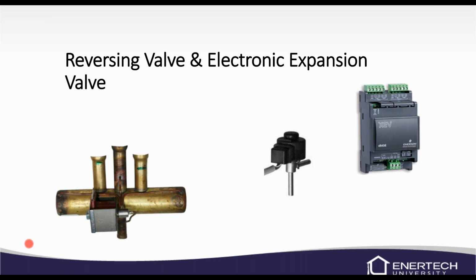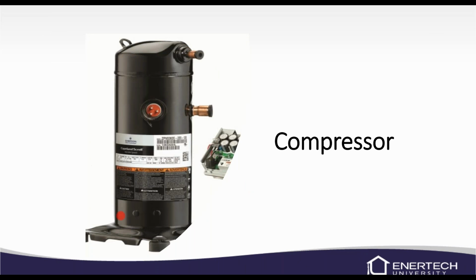We still are using a reversing valve for shifting from heating to cooling, and it is powered in cooling mode. This middle picture here with the little black head, that's your electronic expansion valve. And to the right is the controller for that expansion valve, the XEV controller. Again, this is your variable speed compressor. It doesn't really look a whole lot different than the two-stage scroll compressor. It looks very, very similar. The only thing different is the plug that's going to it, and we've got that white box that's controlling how it runs.